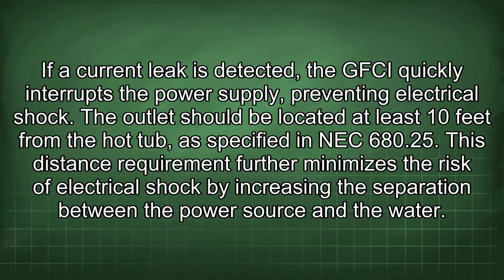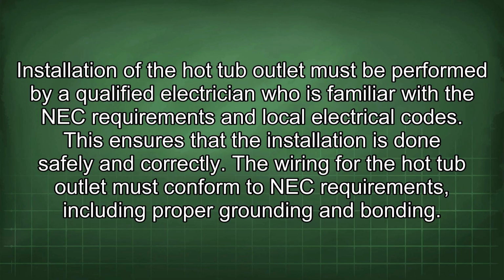The outlet should be located at least 10 feet from the hot tub, as specified in NEC 680.25. This distance requirement further minimizes the risk of electrical shock by increasing the separation between the power source and the water. Installation of the hot tub outlet must be performed by a qualified electrician who is familiar with the NEC requirements and local electrical codes. This ensures that the installation is done safely and correctly.